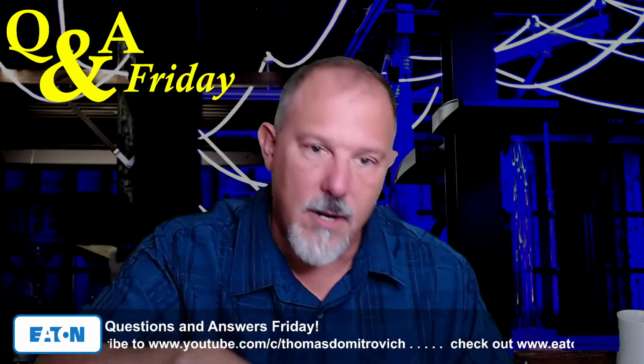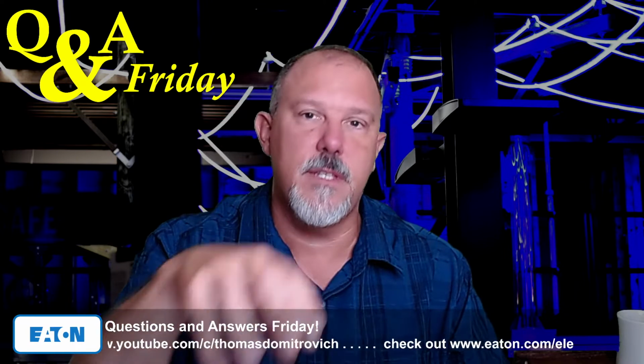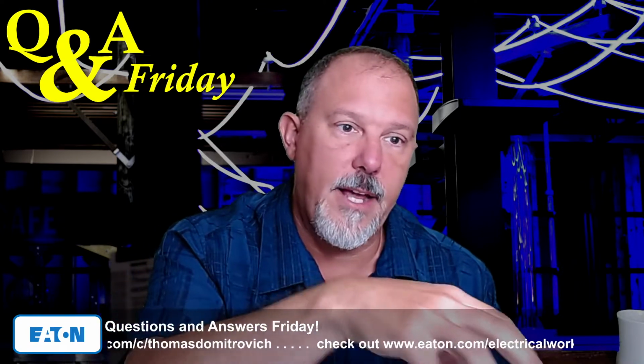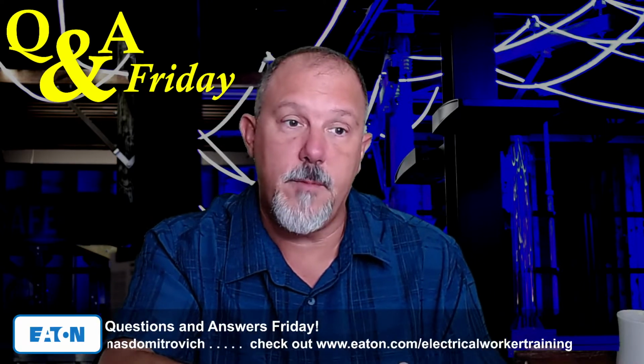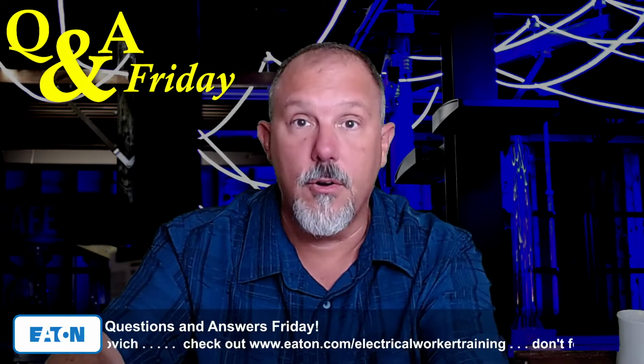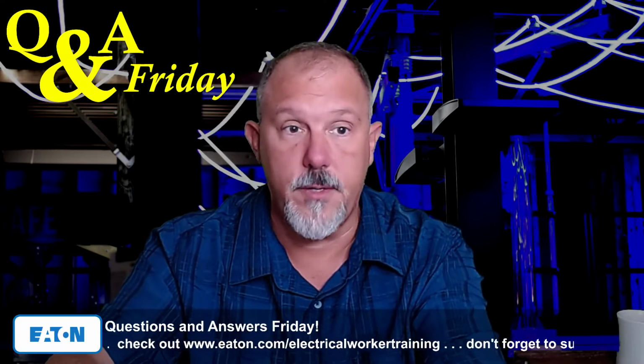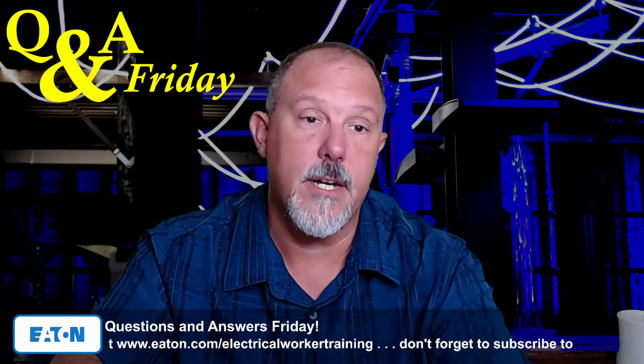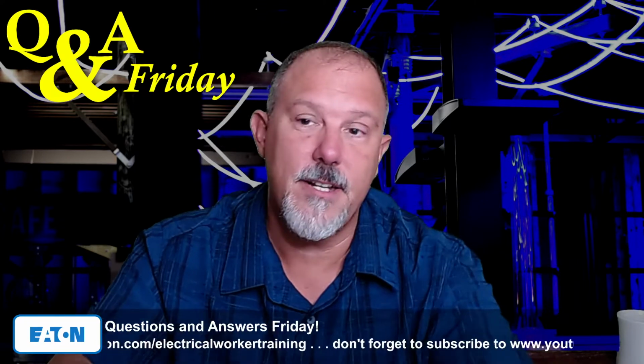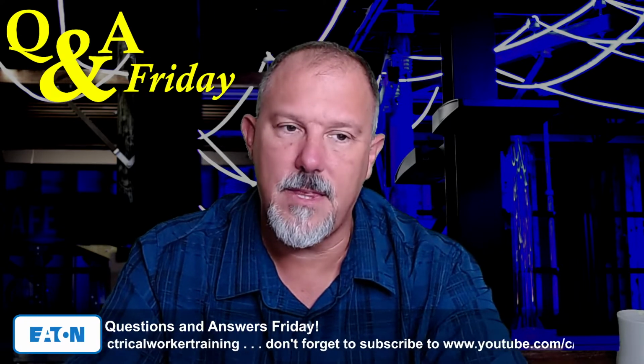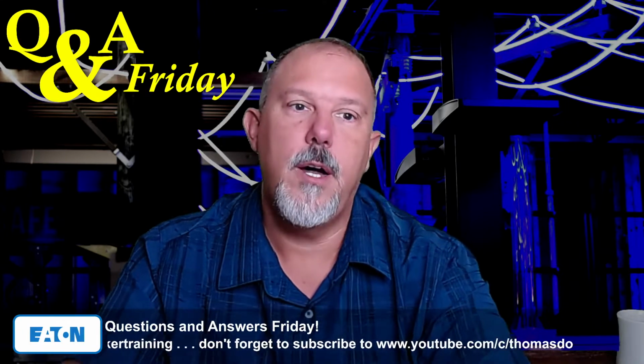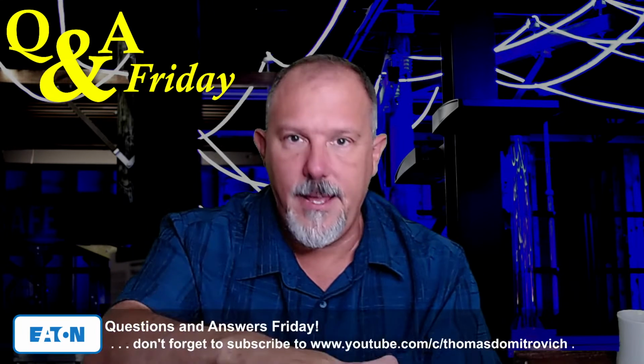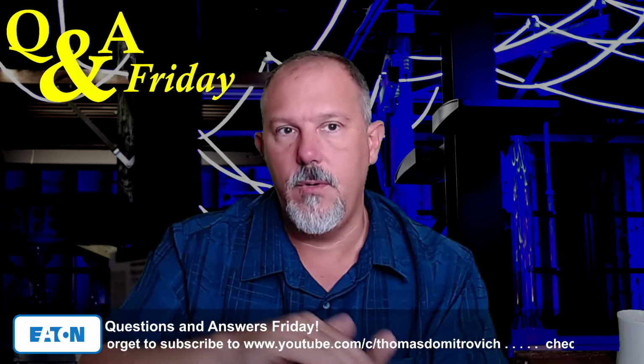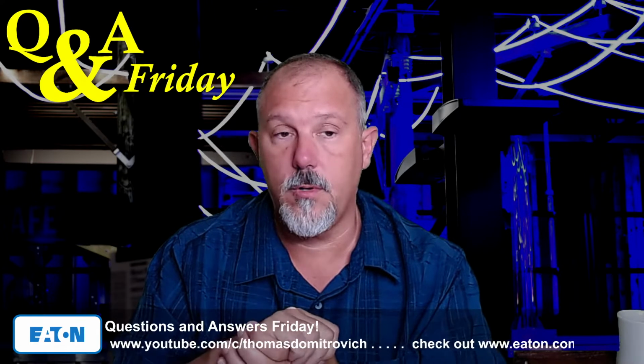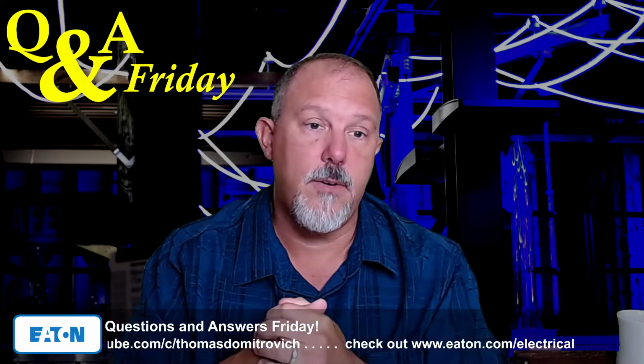So I think the crux of this issue has to be solved in the standards, and the HVAC manufacturers have to make sure they just simply don't violate Article 250 for objectionable currents in the equipment grounding conductor. Don't use that equipment grounding conductor, and I think that this problem would go away. So hopefully the TIA will be successful, and we'll give them a few years to get some stuff in order, and then get back onto the queue, right?